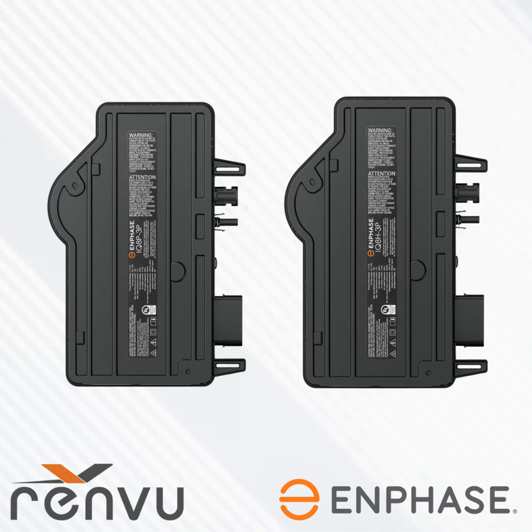All right, so that gateway is powered by a three-phase 208 plus a neutral. We state it needs that neutral wire. The gateway should be installed in the subpanel where your microinverter AC branches tie in. And that gateway, it's the brain of your system. It's going to gather all the information via power line communications from your microinverters and transmit that data off to the cloud.